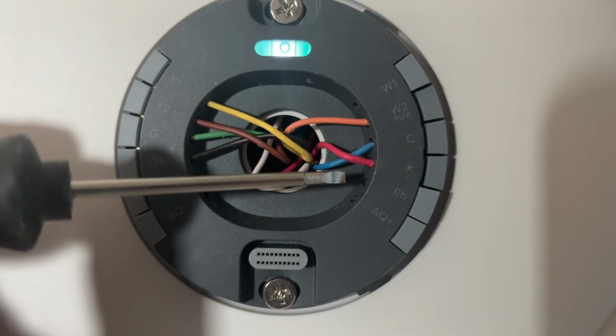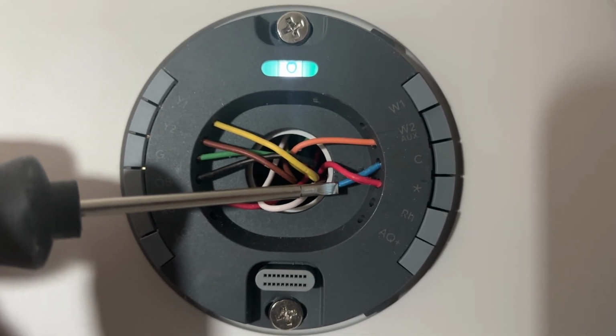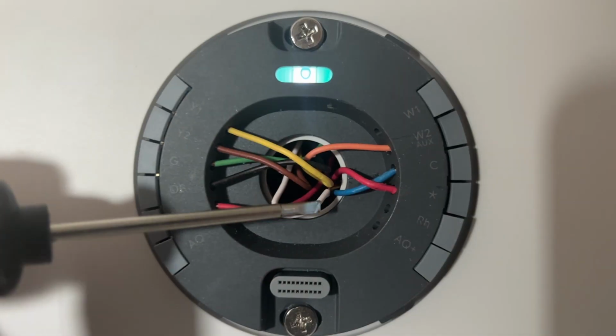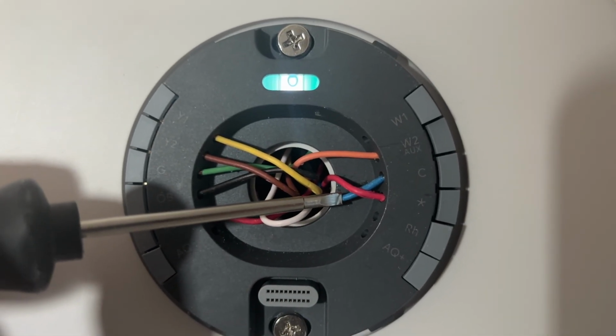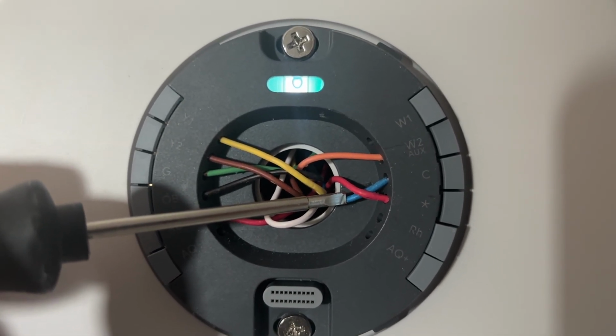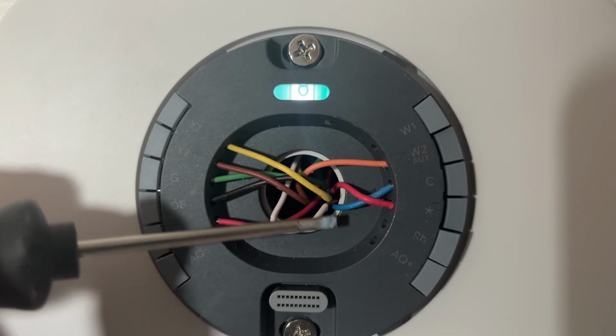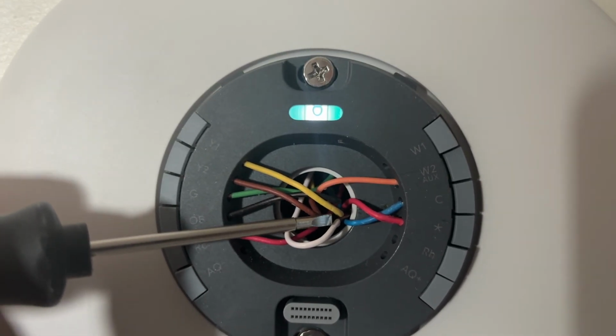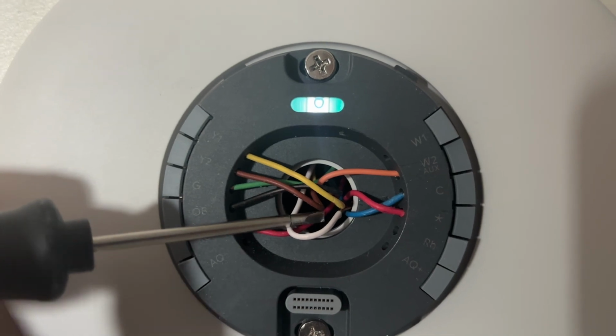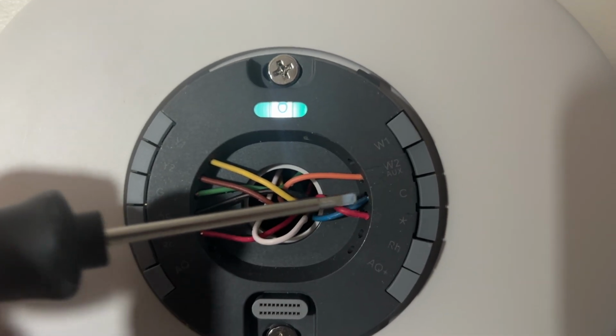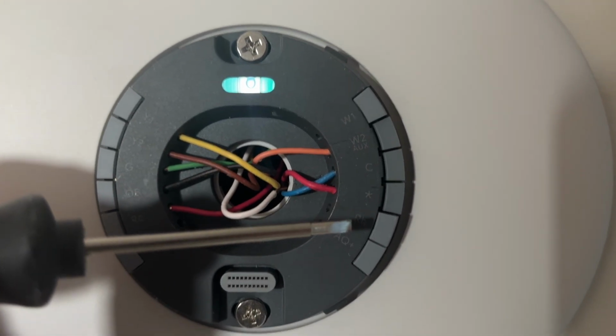C is the common, again, your neutral. And we actually have this neutral wire pigtailed behind here because the dehumidifier needs a neutral or return wire to complete the circuit as well. So the air handler and dehumidifier are pigtailed here. And then I ran that one line into the C.